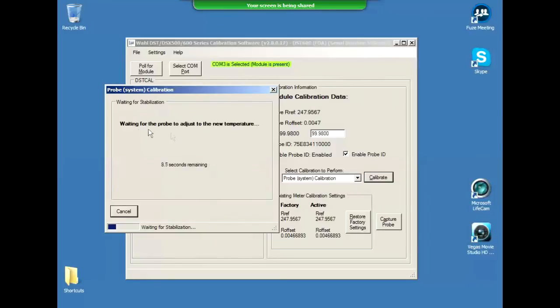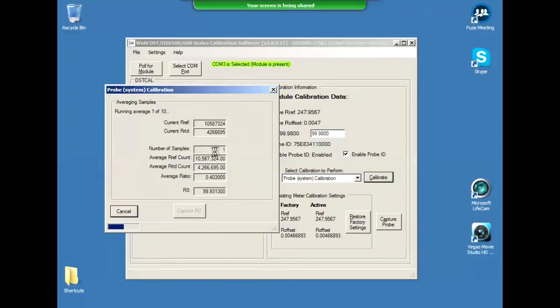It runs through a 10-second stabilization period, and then you'll see a screen pop up with a bunch of numbers in it. What it's doing, this here is telling you how many counts. We take 10 readings, and this is giving us a running average. Once we reach 10 here, this capture R0 button became active. It was grayed out prior to reaching 10.